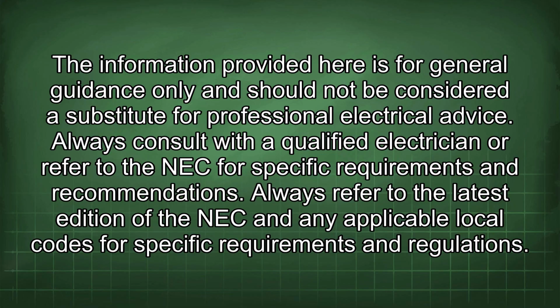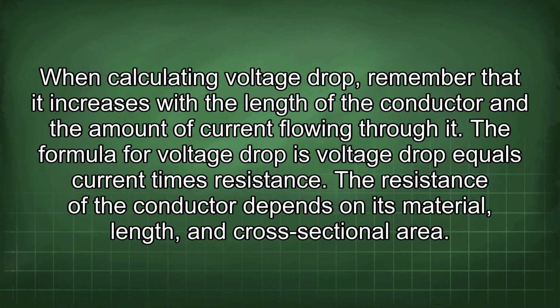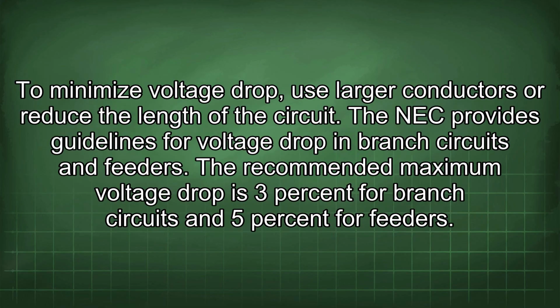specific requirements and regulations. When calculating voltage drop, remember that it increases with the length of the conductor and the amount of current flowing through it. The formula for voltage drop is voltage drop equals current times resistance. The resistance of the conductor depends on its material, length, and cross-sectional area. To minimize voltage drop, use larger conductors or reduce the length of the circuit.